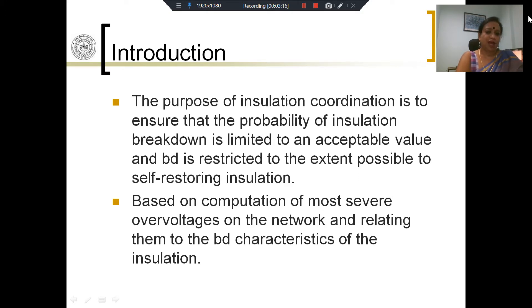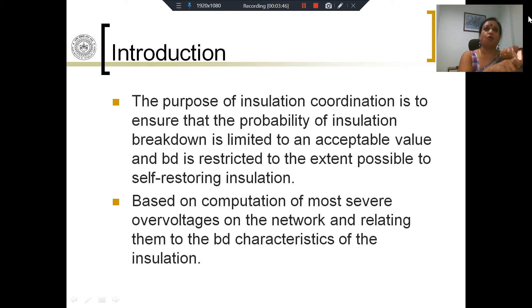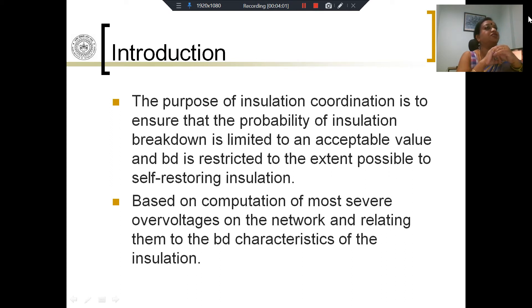To achieve this, we need two things. First, we need to know what kind of overvoltages we expect at various points in the system. Overvoltages will cause breakdown, and therefore it is imperative to know the expected level of overvoltages at the point where the instrument or apparatus is connected. Having understood that, we need to know what kind of insulation is to be provided and what the breakdown characteristics of that insulation are — specifically, whether that overvoltage will cause breakdown of that particular insulation. We are interested in what we call the breakdown characteristic of the insulation, which we will discuss a little later.